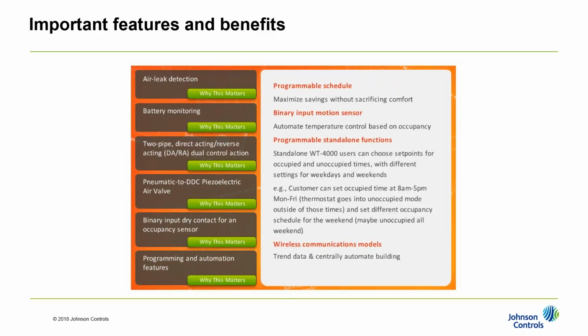In terms of programmability, the same SKU will operate either standalone or in a networked BAS situation. If you have this plugged into Metasys, you get access to all the points and can make it do whatever you want. But if you want to just try these out or do a small zone test, these devices operate standalone, just like your current pneumatic thermostat. You just plug it in the wall, less than 30 minutes as I described before. Within standalone mode, you can get into the programming mode, which has a 5-day, 2-day setup, essentially the work week and the weekend, so you can set it up for your typical operating schedule and get energy savings without even having to network the device.